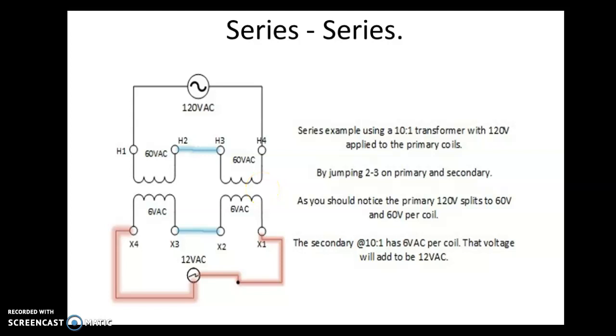When you put the transformer in series, you simply jump out the 2 to 3. So the second terminal on the first coil to the first terminal on the second coil. We're always going to apply voltage to 1 and 4 so that we're using the entire transformer. On the secondary side, you see 6 volts and 6 volts. Once we put our jumper between X2 and X3, we would then connect our load or our meter to X1 and X4.